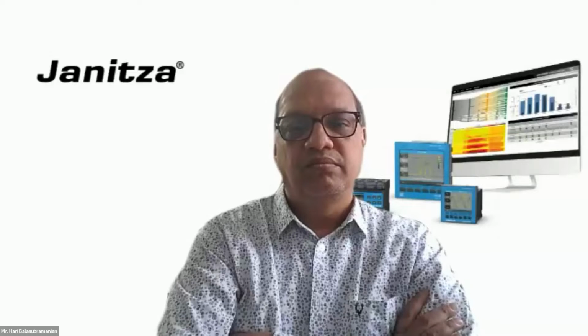Supraharmonics is nothing but an extension of harmonics, well beyond the 2.5 kilohertz that we are currently trying to measure using the existing equipment. Most of the equipment is designed to measure THD of voltage and current for up to the 50th harmonic. Only a few new equipments, under Fluke and also the PQ box, have incorporated the new measurement for supraharmonics, which is up to 150 kilohertz. The reason is that equipment like LEDs, electric vehicles, some LCD TVs and solar inverters are all emitting frequencies well beyond 10 kilohertz.